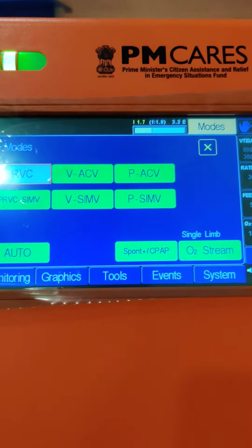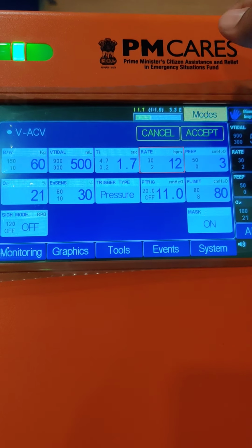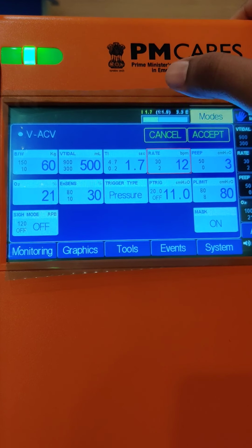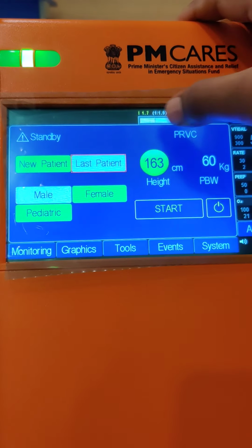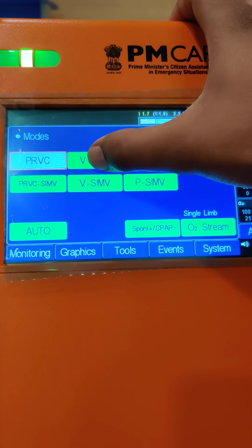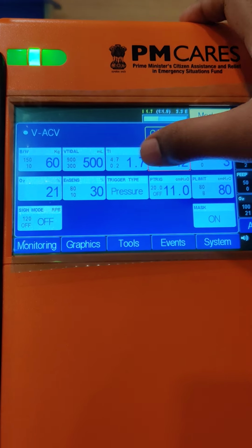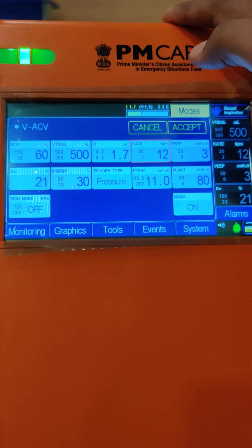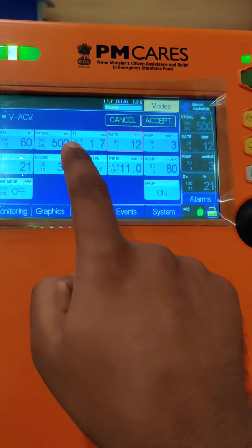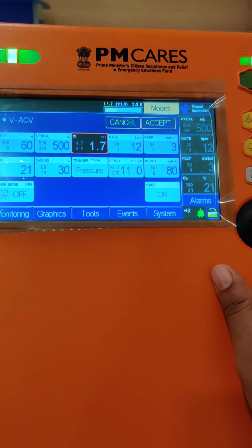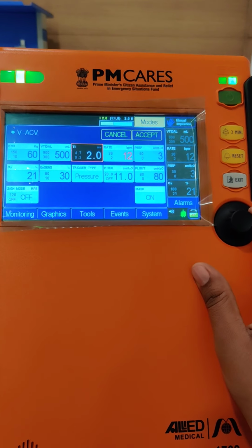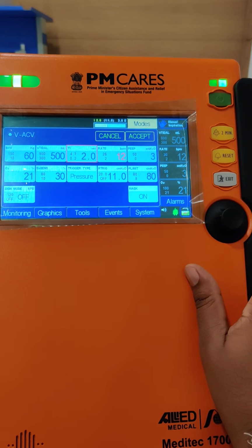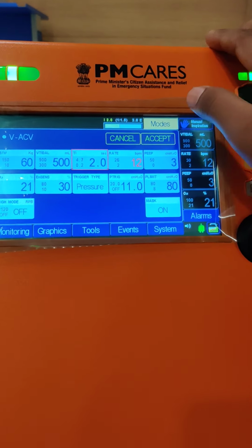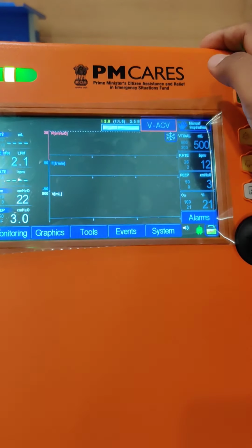Now discussing the other modes of ventilation, we have this volume assist control ventilation. When I press this VACV, it will go into the VACV settings. Whatever settings have to be delivered to the patient, you can change them. You can select the parameter and change it according to the requirement, and for confirming you have to press this confirm key, and for entering into the mode you have to press the accept key.